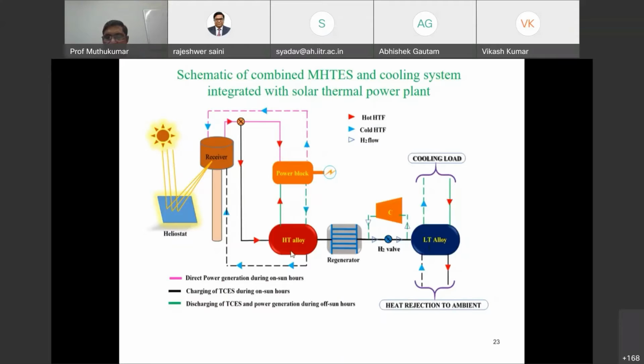Let us assume you are desorbing hydrogen from the high temperature alloy at about 5 bar pressure, as an example. The corresponding desorption temperature may be around 350 degrees Celsius. Then you allow the hydrogen to absorb at the low temperature alloy around room temperature, say 35 degrees Celsius, at 5 bar. This heat can be rejected to the ambient, which acts as a heat sink. This is your charging mode, where you are charging the hydride in the system.